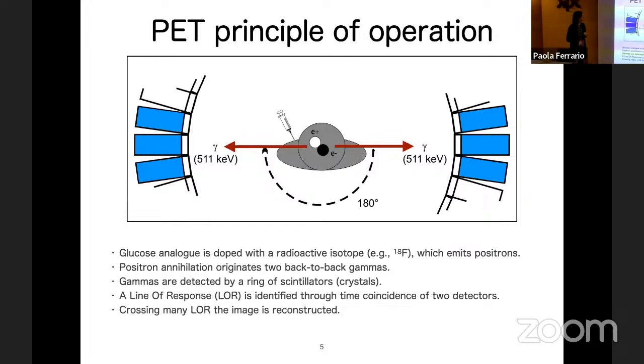So what one has to do is to surround the patient with a ring made of photon detectors. So if you detect in time coincidence these 2 photons, for instance, in this detector and in this detector, you can draw a line and you know that your photons have been originated in some point of the line. So crossing a lot of these lines, one is able to make an image of the origin of these gammas, so of the area where the metabolism is higher.